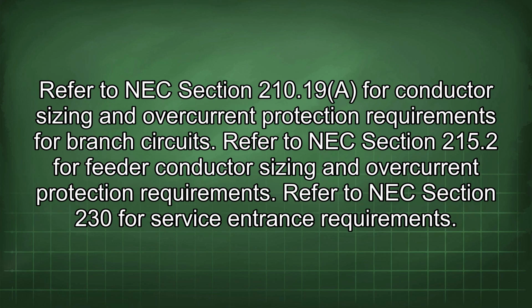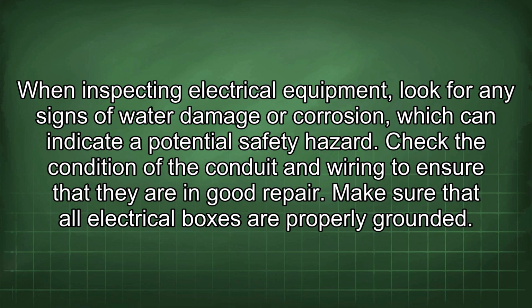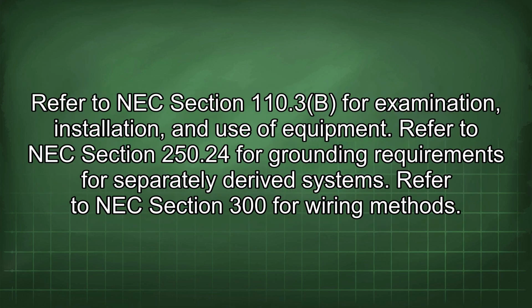Refer to NEC section 210.19 for conductor sizing and overcurrent protection requirements for branch circuits. Refer to NEC section 215.2 for feeder conductor sizing and overcurrent protection requirements. Refer to NEC section 230 for service entrance requirements. When inspecting electrical equipment, look for any signs of water damage or corrosion, which can indicate a potential safety hazard. Check the condition of the conduit and wiring to ensure that they are in good repair. Make sure that all electrical boxes are properly grounded. Refer to NEC section 110.3(B) for examination, installation, and use of equipment.